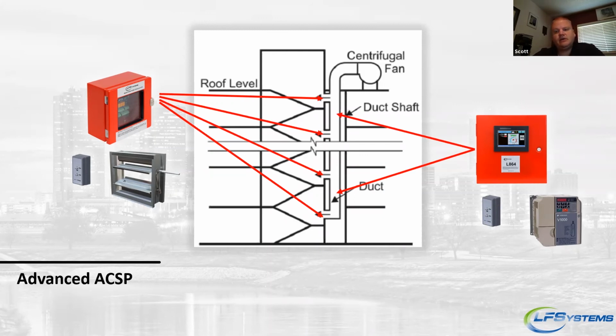Basically, you would zone this out. So we recommend every 2 floors having a zone. NFPA allows up to 3. Anything beyond that requires a smoke study. So basically, you would have an injection point damper at each section, and these independent L850 controllers would modulate the damper according to the needs of that zone.